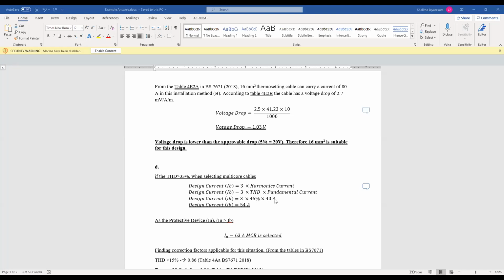In here 45, and we are going to multiply 45 into 40 amps. 40 amps is the fundamental current. So if you multiply these two values, you will get the harmonic current. So in the neutral, there will be 3 times the harmonic current. Because if you have third harmonics, our harmonics will add up, right? So there are three phases, and all the three phases will have this much harmonic current. In the neutral, they will add up, so creating 3 times the current.